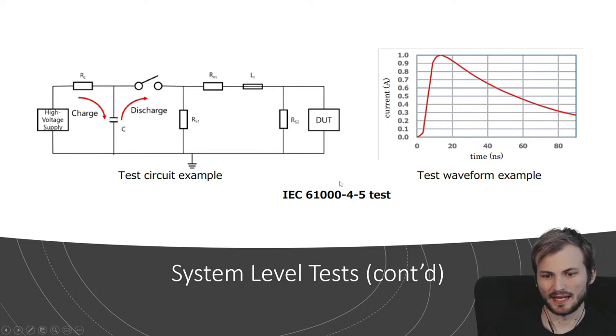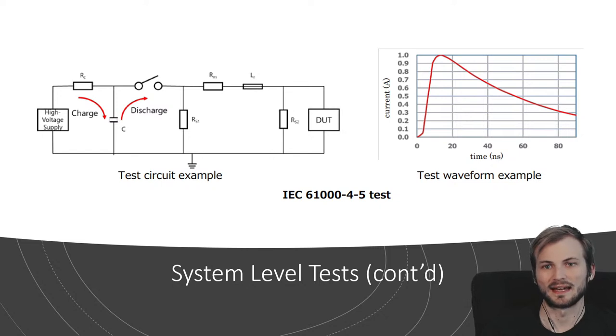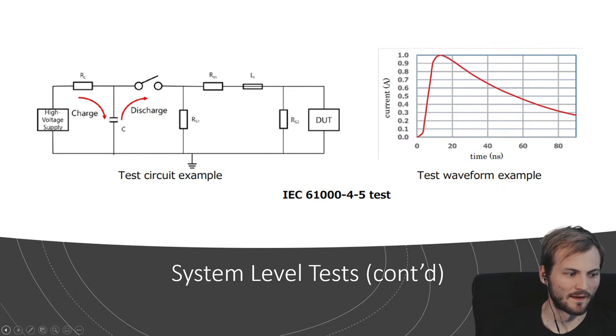So again, these you're designing towards if you have a specific standard that either you're required to by law, or whatever device you're doing is going into an environment that requires it. You're normally not ever saying, oh, I want it to pass this standard. It's normally you get told it has to pass this standard and then work back from there.